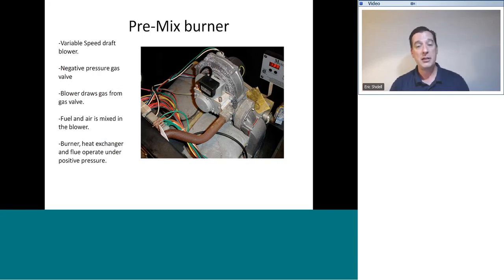The big difference, though, is that on the premix burner, gas is introduced to the suction side of the blower, the inlet side of the blower. It is not introduced into the discharge side of the blower. Fuel is introduced to the suction side of the fan. This is a variable capacity modulating premix burner. In fact, that is one of the great advantages of premix burners, they can very easily be modulating burners. And you'll find them very commonly on modulating and condensing boilers, modcon boilers. Very common on lots of water heating type appliances. If you're a Lennox dealer and you're familiar with the Complete Heat, it had a premix burner on it. This is a picture of a Munchkin boiler, which has a premix burner.